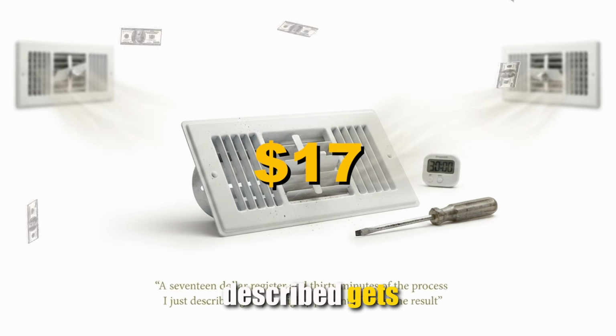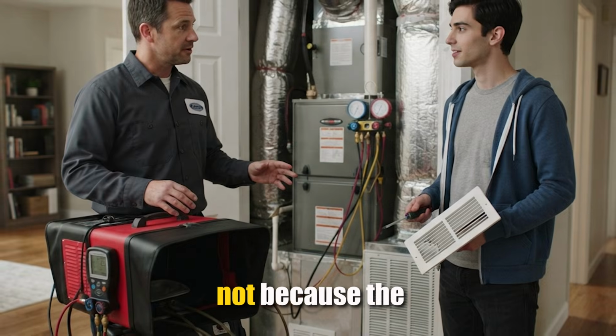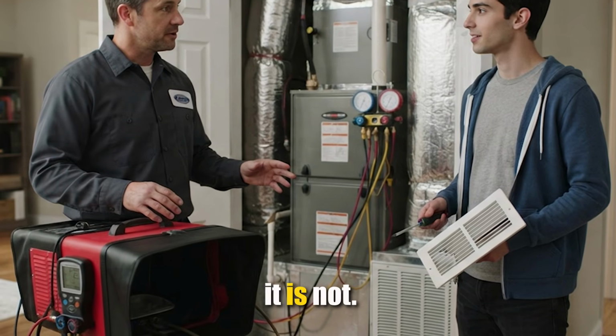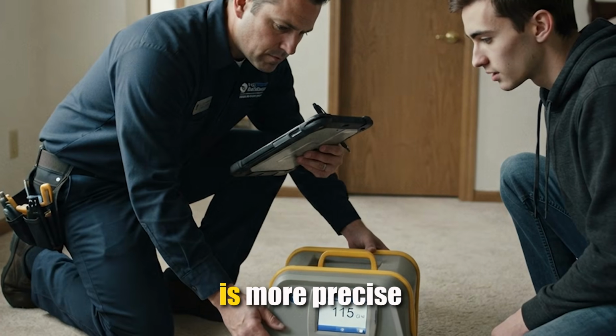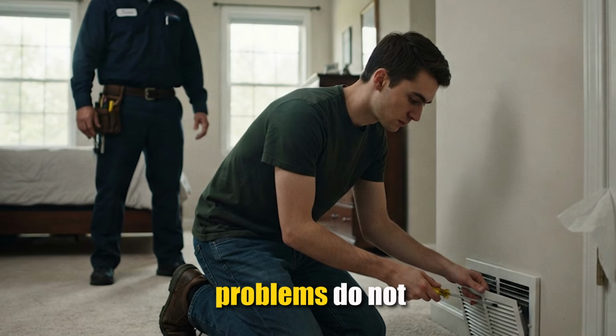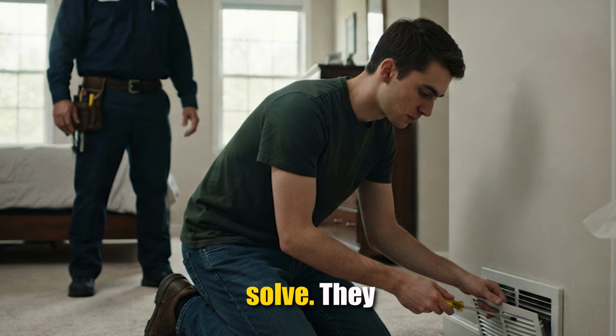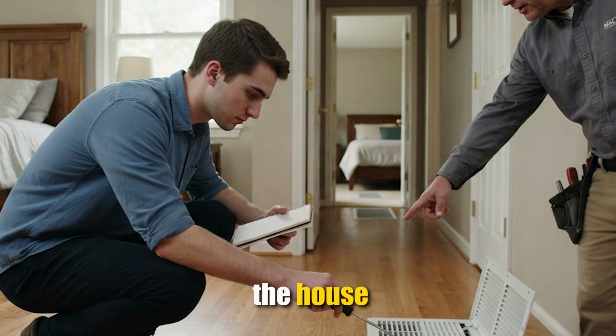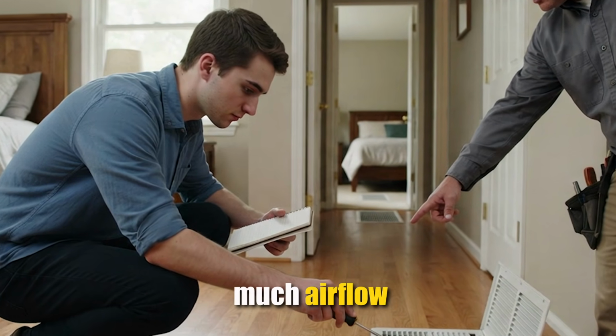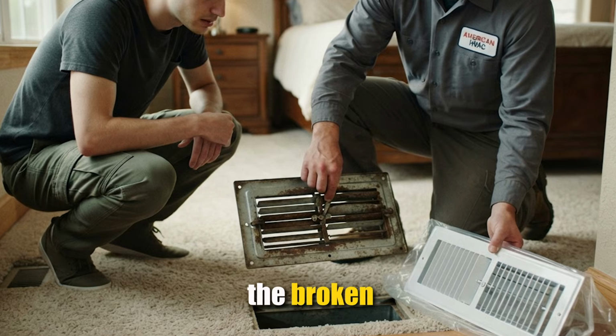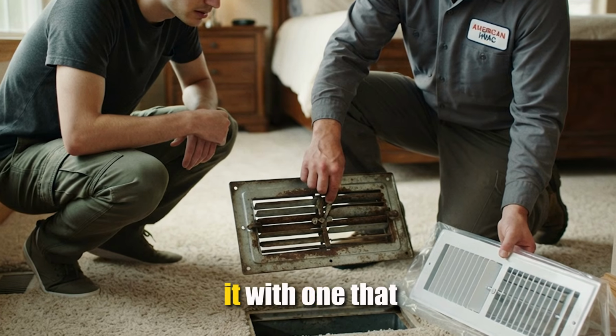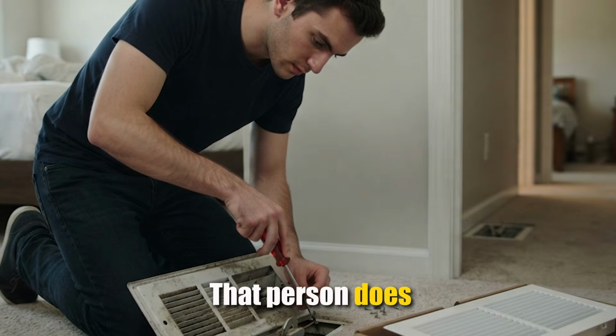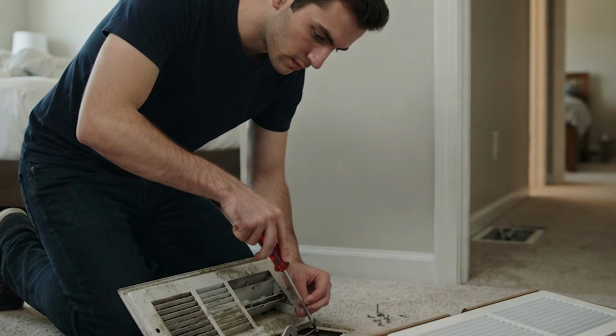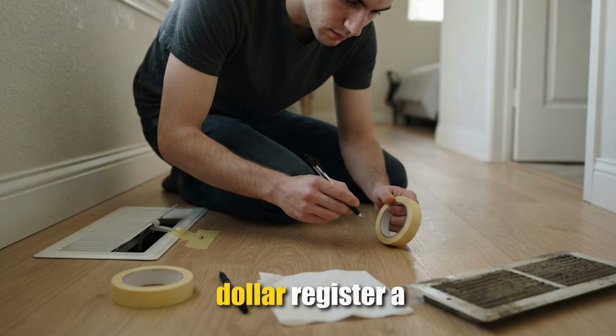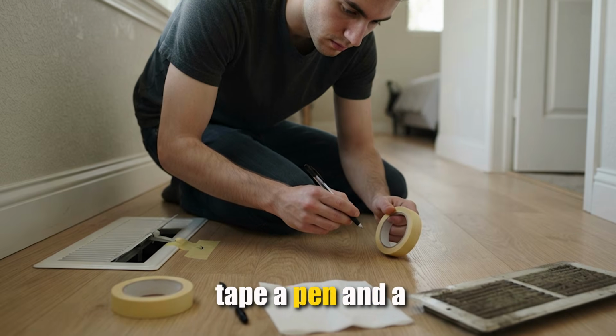A $17 register and 30 minutes of the process I just described gets you 80% of the same result. Not because the process is identical, it is not. A professional with a flow hood is more precise, but most hot room problems do not require precision measurement to solve. They require someone to walk through the house, identify which rooms have too much airflow, restrict it moderately, verify the broken register in the problem room, and replace it with one that actually works. That person does not need to be a licensed HVAC technician. It needs to be you, with a $17 register, a roll of masking tape, a pen, and a piece of tissue paper.